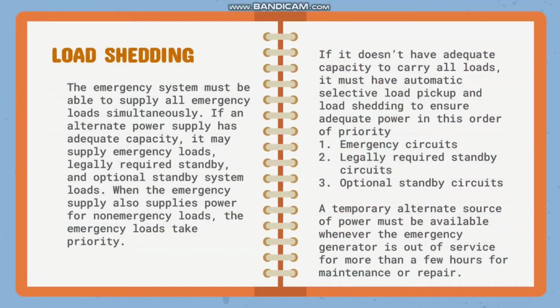So, next, load shedding. The emergency system must be able to supply all emergency loads simultaneously if an alternate power supply has adequate capacity. It may supply emergency loads, legally required standby, and optional standby system loads. When the emergency supply also supplies power for non-emergency loads, the emergency loads take priority. So in simple words, load shedding is an act or process ng pag-disconnect ng electric current sa certain lines kapag yung demand is mas mataas kaysa dun sa supply. So kapag nagkaroon ng kakulangan sa alternate power supply, syempre ang i-disconnect is yung mga non-emergency loads at ang ipa-priority is yung mga emergency loads.